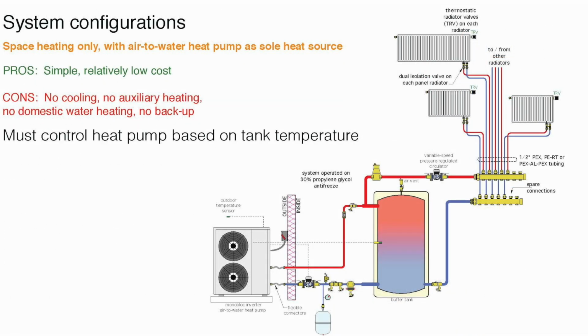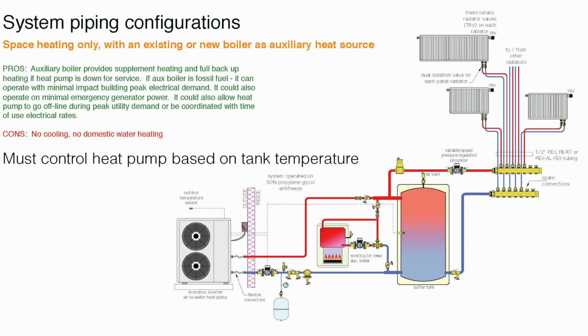Real quick, I'll run through these things. There's an air-to-water heat pump, a monoblock. It goes into a buffer tank, and over on the upper right is a manifold, some PEX tubing, and panel rads. There's a variable speed circulator right here that just goes up and down as the thermostatic radiator valves open and close on those radiators. It's really a simple system. It's a heating-only system, though, okay? So it's a very basic system. Now here's where we've kept, or we've put a new boiler in the system. It's just the boiler's in parallel with the heat pump. And your control system decides which one operates, or possibly both at the same time. All right? It's just in parallel.